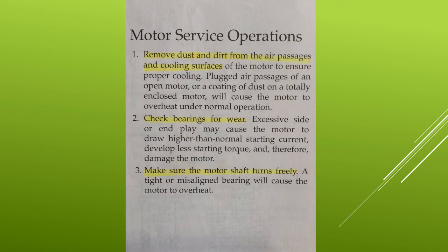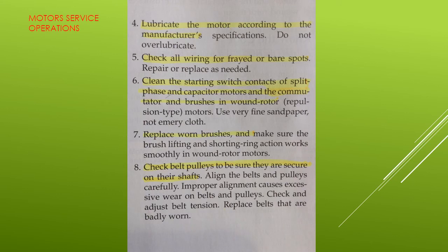Step three, make sure the motor shaft turns freely. A tight or misaligned bearing will cause the motor to overheat. Lubricate the motor according to the manufacturer's specifications. Do not over lubricate. Five, check all wiring for frayed or bare spots. Repair or replace as needed. Six, clean the starting switch contacts of split phase and capacitor motors and the commutator and brushes in wound rotor and repulsion type motors. Use very fine sandpaper, not emery cloth. Seven, replace worn brushes and make sure the brush lifting and shorting ring action works smoothly in wound rotor motors.